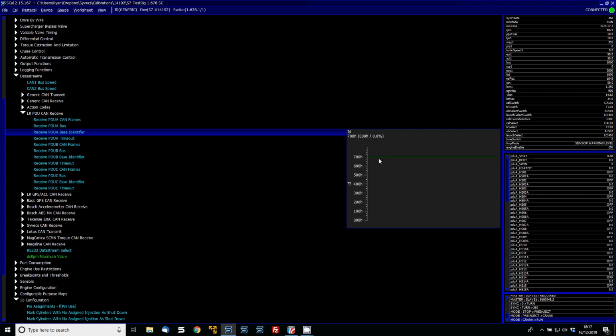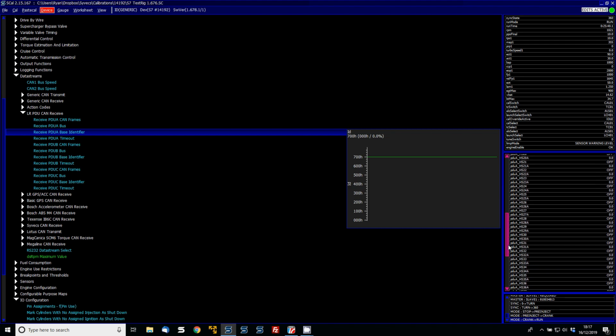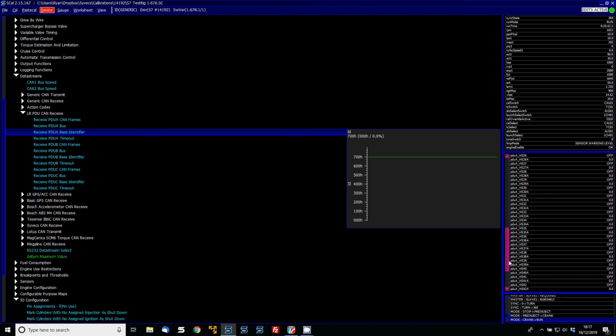It's generally worth starting with 00 as the base, because the PDU will send up to 20 items of frame data containing all the current values and status data from the PDU. So when you enable those, all of the PDU A pins will be sent over, all the way from PDU 0 or 1 up to I think it's 48.